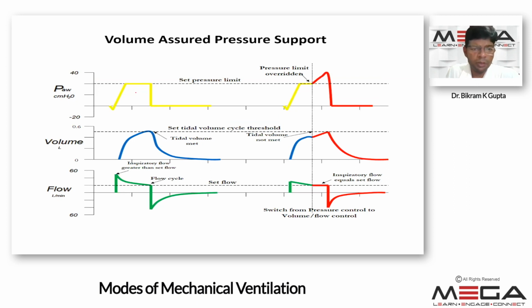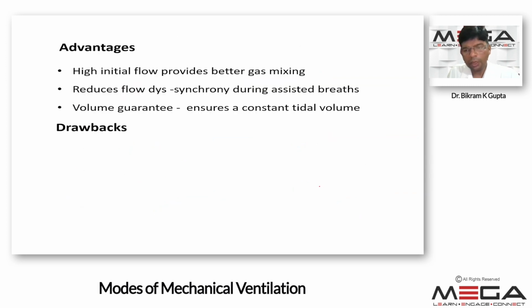Look here in this diagram. We have to set the pressure limit, and then with this pressure limit, the set tidal volume cycle threshold is achieved. Because of this pressure, we are putting the patient in the pressure mode, pressure support ventilation. So this flow is the descending type of flow. But look here, the tidal volume is not met. Because of that, the descending flow is changed into a constant flow to achieve the tidal volume which an operator sets in the ventilator. That tidal volume is achieved by increasing the pressure limit, so the pressure limit becomes the override. Look here, there is a change of the mode of ventilation intra breath. Here is the pressure support with descending flow, and now the descending flow changes to constant flow, that is the volume support, to achieve the target volume.